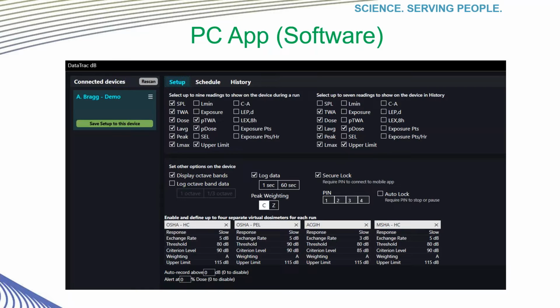When you open the software and select the device you want to download and/or set up, the DataTrac dB software comes to that Setup tab. Now you can just select the boxes and parameters that you want, and the green tab below the device, in the upper left-hand corner, will change to let you know that you're ready to save this to the device. Now I'm going to back up a little and walk you through more information, but I just wanted to show you quickly that it comes straight to that screen so that you can set up the parameters and the device the way you want and send it to the unit.